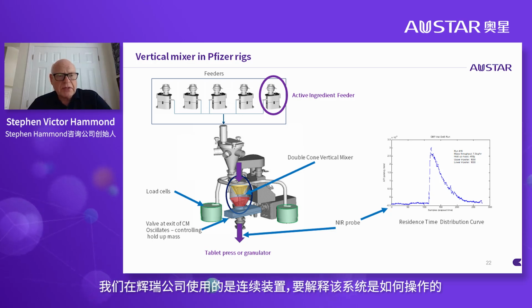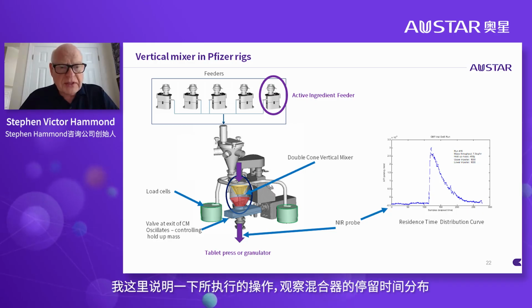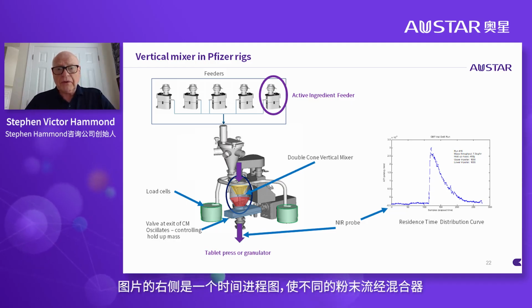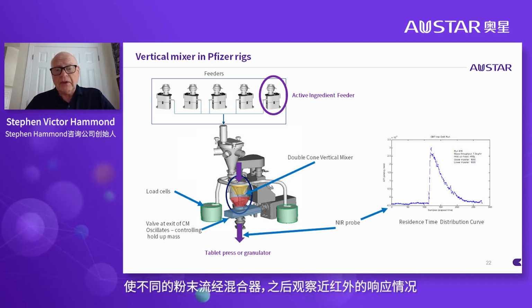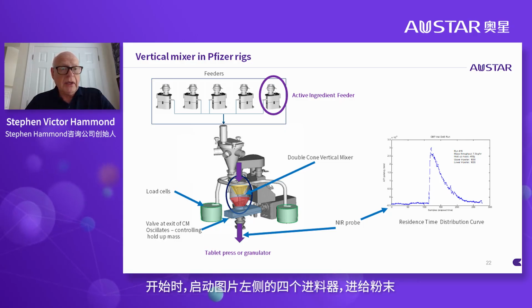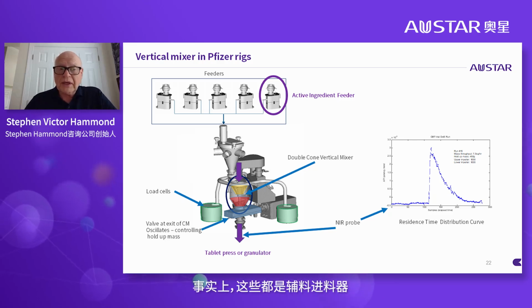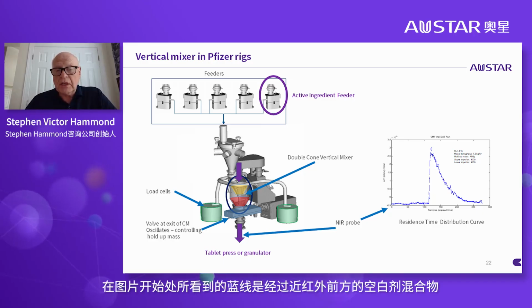And to illustrate how this system works, I'm illustrating an exercise that was performed to look at the residence time distribution of the mixer. So this plot on the right-hand side is a time course where we ran different powders through the mixer and then looked at the response we got from the near-infrared. To begin with, just the 4 feeders on the left-hand side were activated and feeding powder. In fact, they are all excipient feeders. And so essentially the blue line you see at the beginning of that plot is a placebo blend passing in front of the near-infrared.